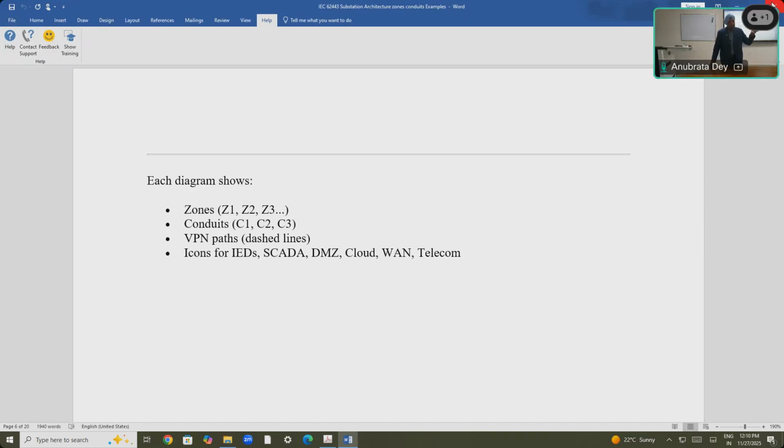Yeah. So that's in zone one. That's in zone one. Yes. Yeah. So you can go through zone two and get that information. You need? Oh, fault recorder. Yeah. Yeah. So you can go through zone two, or another way is to set up the virtual LAN. Remember we talked about virtual LAN, and you can include that component as a part of zone one. Although physically it may reside somewhere else, right? But as a part of virtual LAN, you can set that. Okay. There are ways of doing that. If that's the requirement, you could do that. You could either go through zone two, or you can make that particular workstation as a part of your virtual LAN.